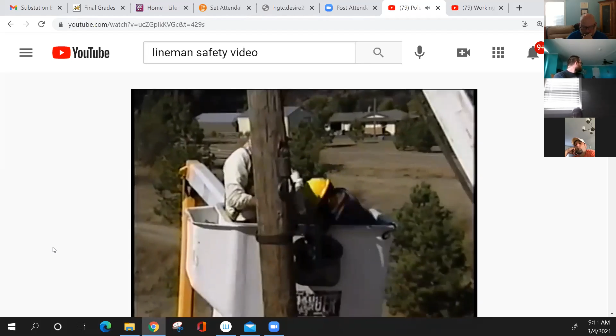An alternate method to chunking is the single section method, where the top of the pole is removed in one large piece. The bucket and line truck are stabilized at safe distances from each other, with the pole easily accessible from either truck. The boom of the line truck is placed near the top of the pole where the single section will be removed. The two employees in the bucket take up a sling and attach it near the top of the pole using a choker attachment.